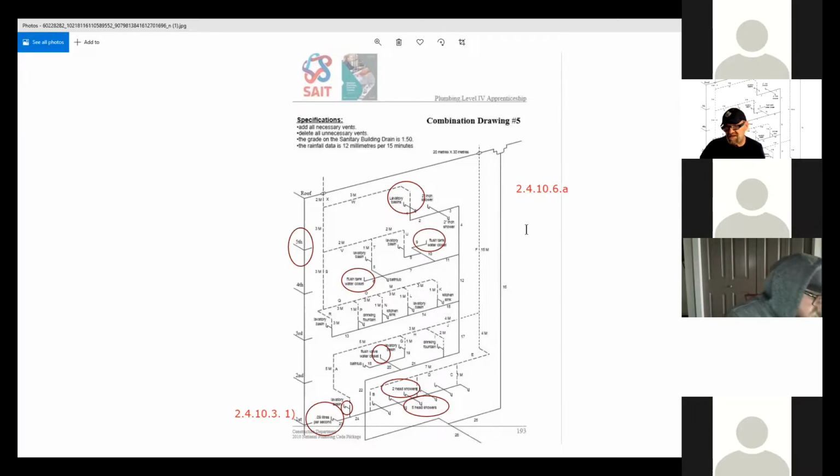So on the soil or waste stack table, you've got 3 columns. The column on the right, the farthest on the right, is from any 1 story. Can everyone see that? From any 1 story on the soil or waste. If you look at any 1 story, if you exceed 18 fixture units, that stack is going to be 4-inch below there, right? More than 18 fixture units is going to equal a 4-inch stack.